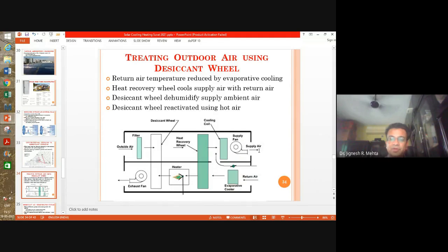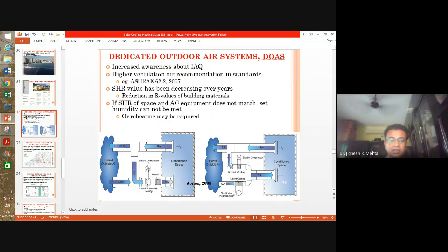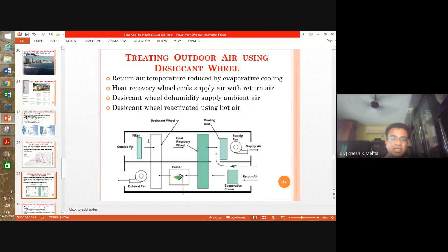And then heat recovery. As you have seen, you are exhausting the conditioned air, which has low enthalpy, right? With the consumption of power, you have reduced the enthalpy, but then you are just throwing it out, which is not a wise thing to do. So that exhaust air, the lower circuit, you should try to utilize the low enthalpy of that and only put it back into the atmosphere after that. With the help of that, you reduce the temperature and humidity of the outside air that you are taking. So the more outside air you want to take in a centralized air conditioning system, the more useful and beneficial this becomes, right?